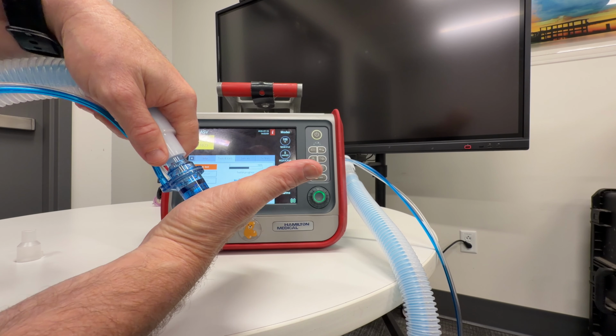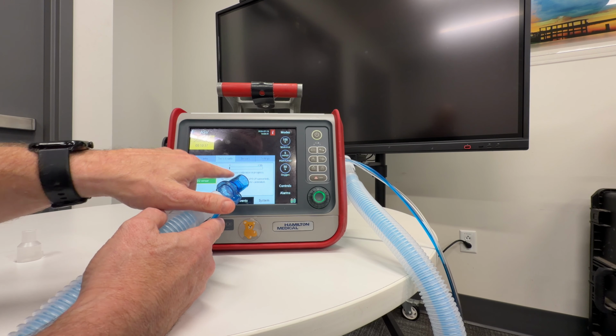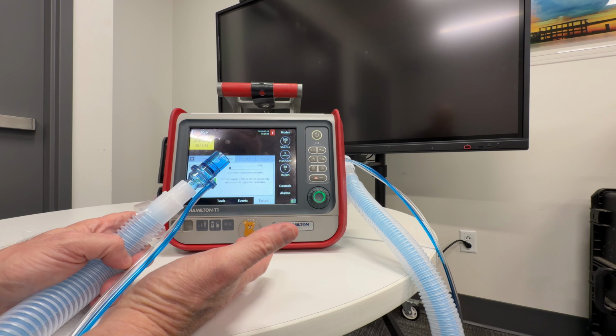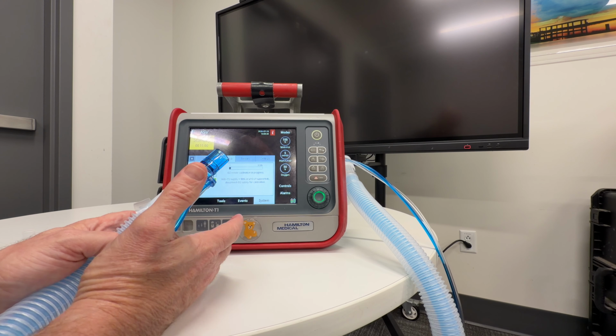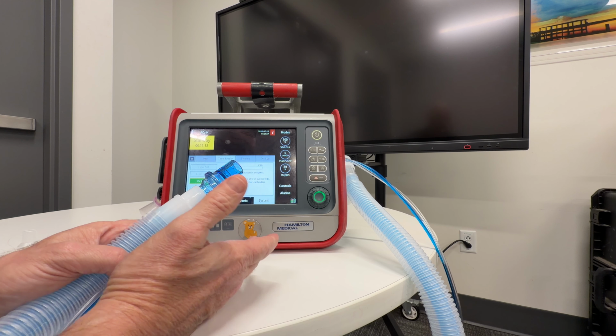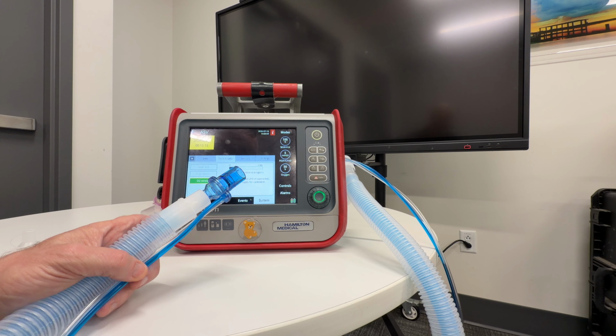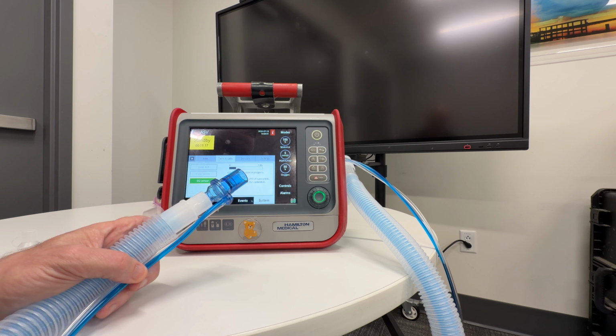Now, every now and then you'll have to do an O2 cell sensor check. So for some reason this will happen. Somebody probably could tell me why, I don't really know. But you simply disconnect it from the patient, and you hit O2 sensor, and it's going to say to turn the O2 down below 99% or disconnect the O2 supply. That's what I normally do. I seem to have less problems. Now I'm going to spare you the time it takes for this to actually do, but a lot of times it'll go up and it'll go up to 100%. It takes a couple minutes and it will pass. If it doesn't pass, you've got an O2 sensor that needs calibration. You'll have to actually bring it in and go to the shop with it.